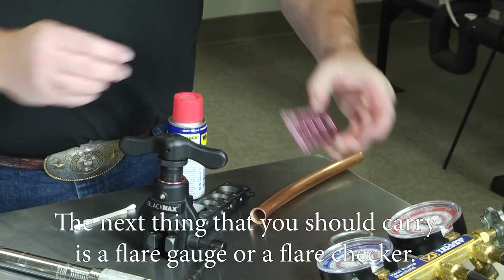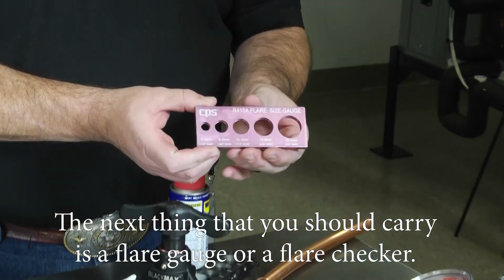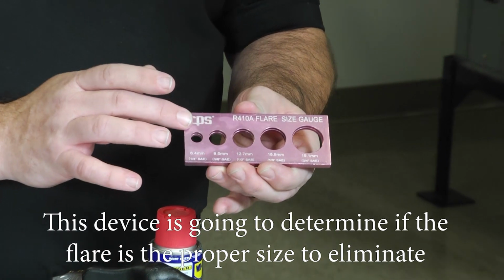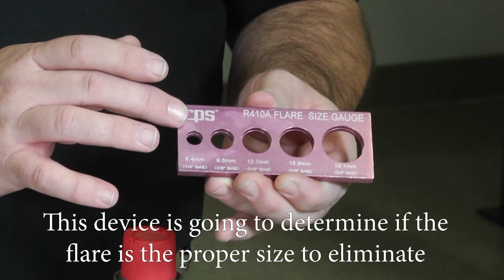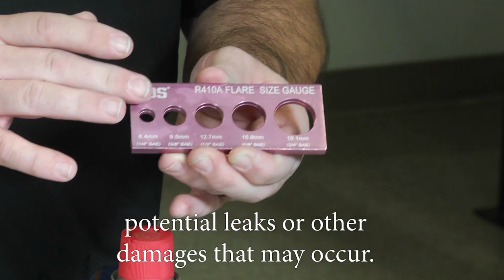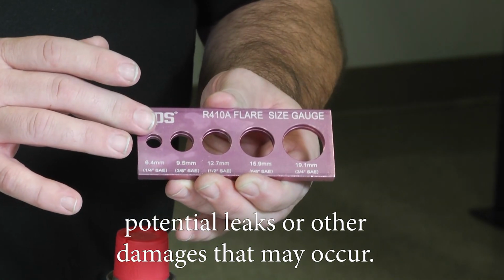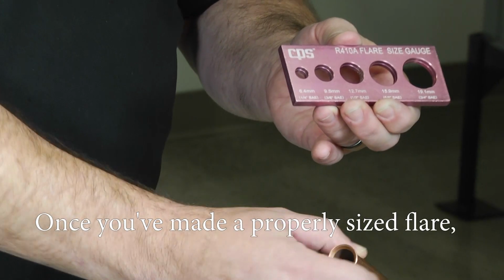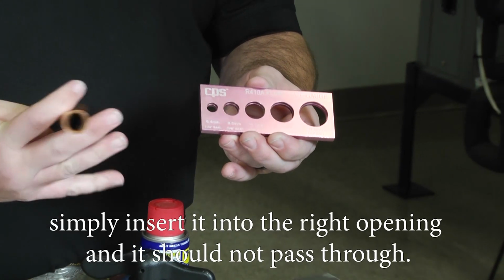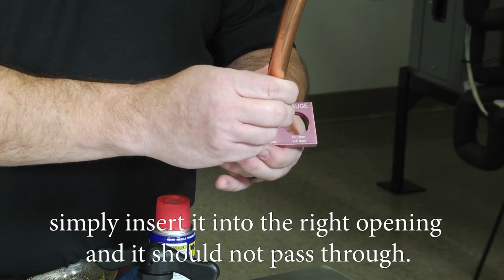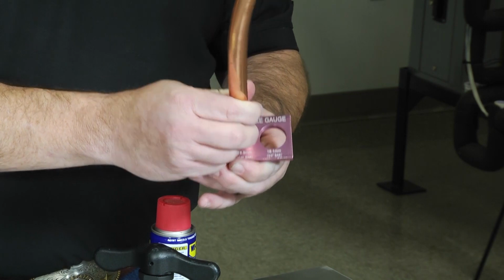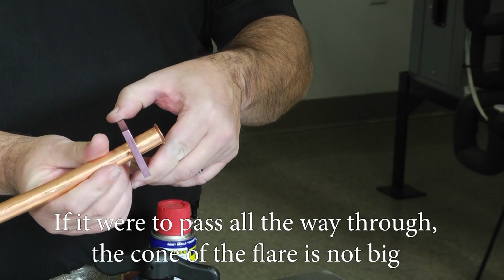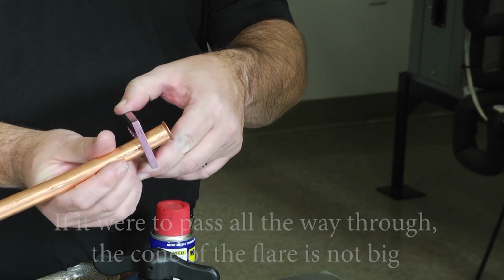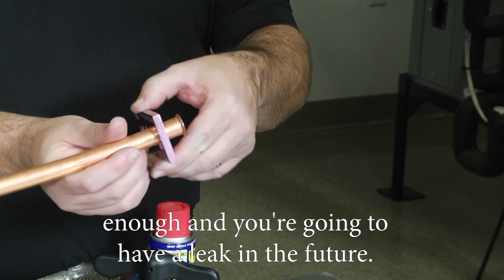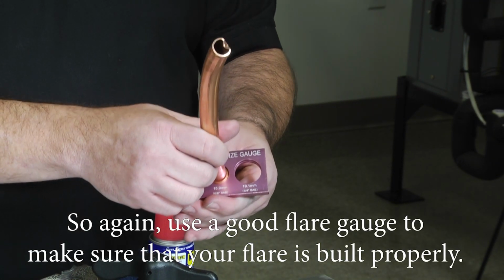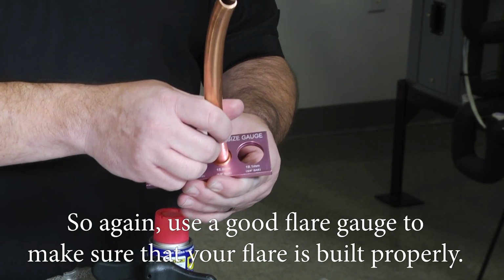The next thing that you should carry is a flare gauge or a flare checker. This device here is going to determine if the flare is the proper size to eliminate potentials for leaks or other damages that may occur. So once you've made the proper size flare, simply insert it into the right opening and it should not pass through. If it were to pass all the way through, the cone of the flare is not big enough and you're going to have a leak in the future. So again, use a good flare gauge to make sure that your flare is built properly.